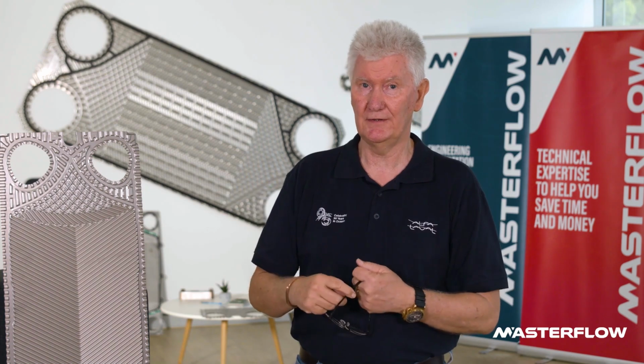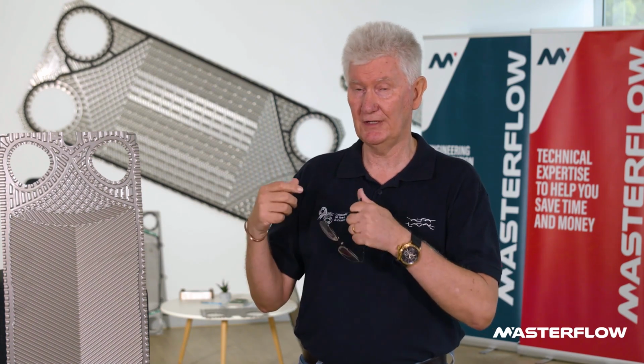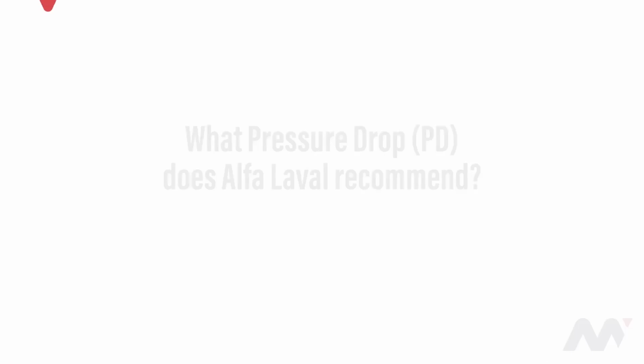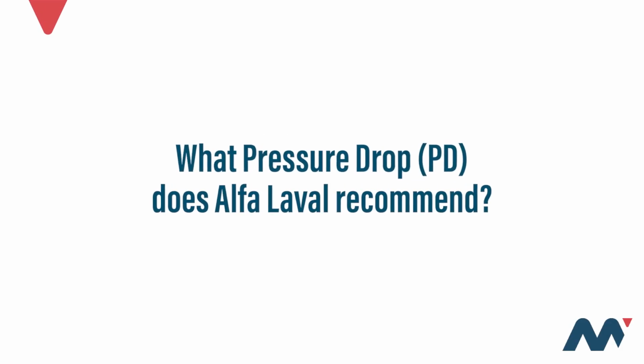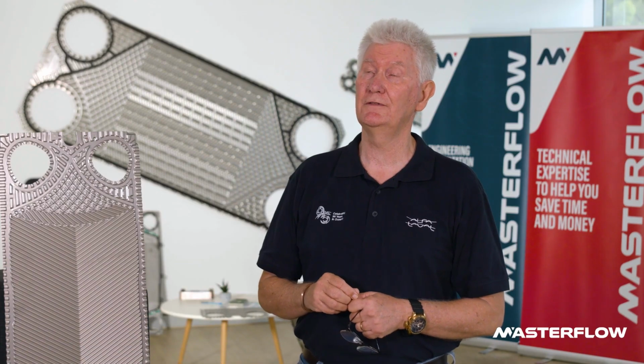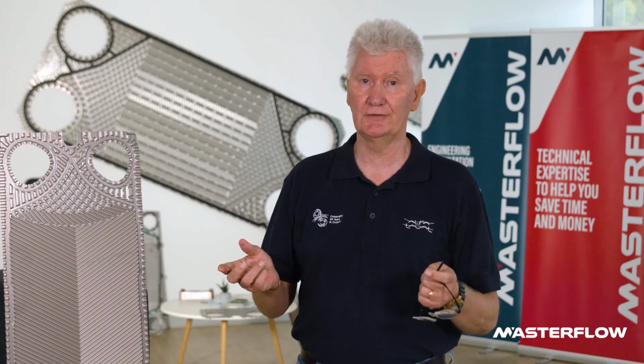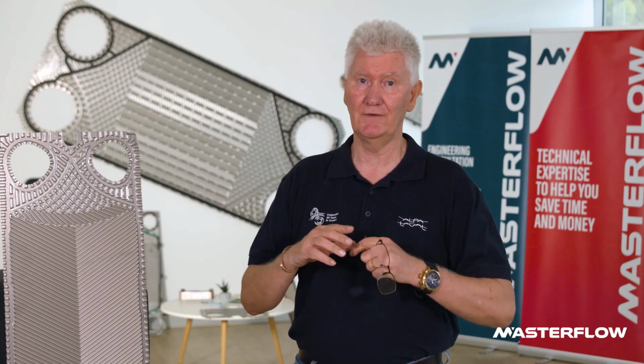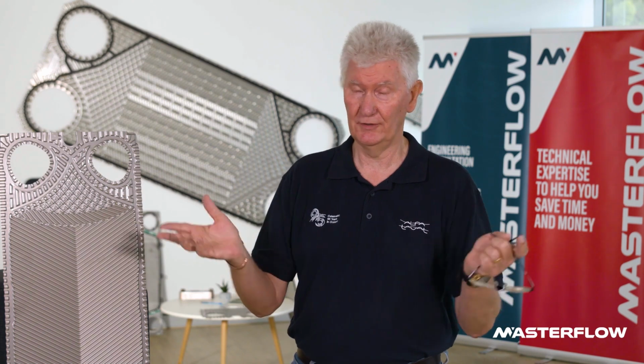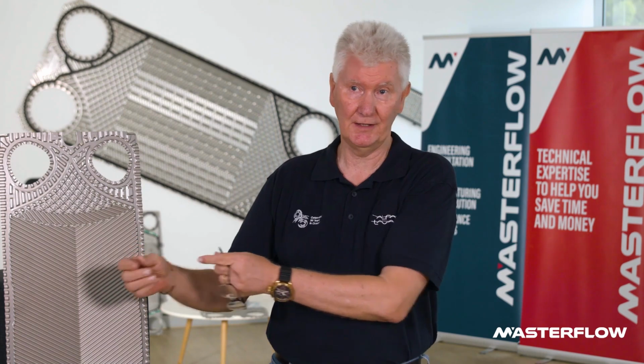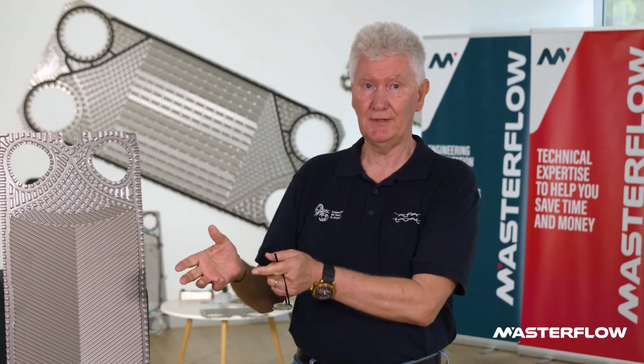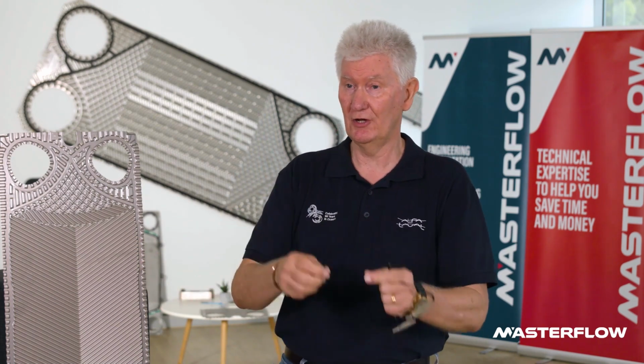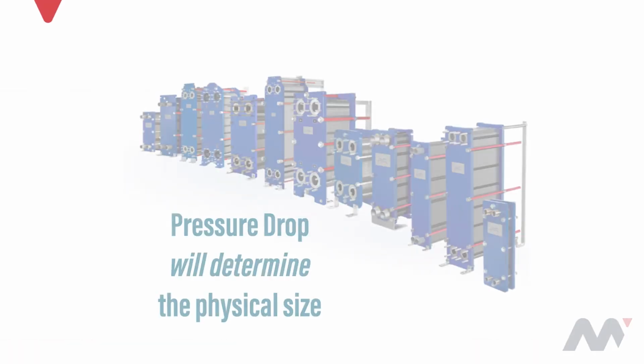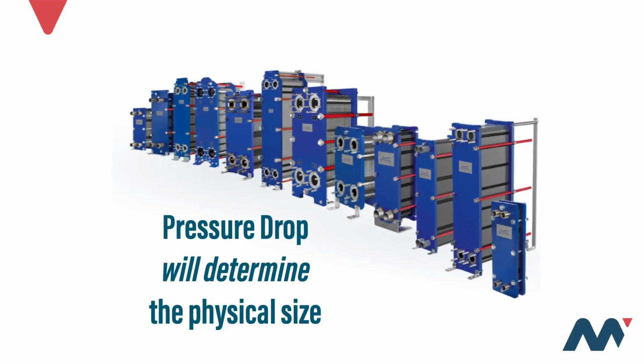So one has to look at the type of water, how you're achieving the heat transfer area, and in regards to how the heat exchanger is going to foul up over time. In the norm, Alfa Laval will design the heat exchangers at around 100 kPa if we are not given any limits. That's just a normal thing we do, but it could easily be 125 kPa or 75 kPa. If a client says we want 10 kPa, we will design for 10 kPa and show them the difference between 10 and 20 kPa. There's a huge difference in the size of the heat exchanger.